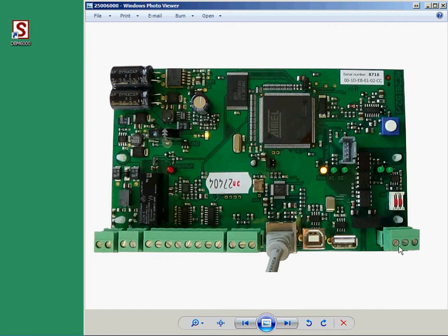In the right corner we have the bus in and out, and we have a ground wire, not the negative pole, but the earth wire, which has to be connected to ground 1. The jumper here is the termination of the bus, so if this is the start of the basic string, these two red things have to be pushed up, so we have 180 ohms over the bus.